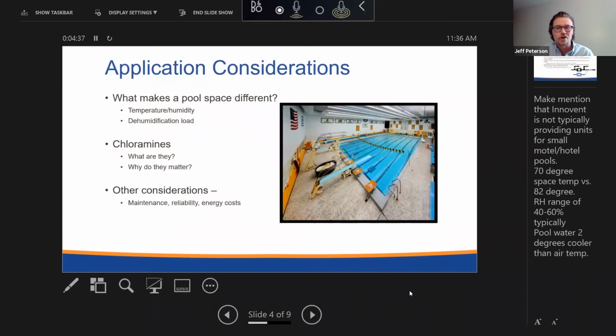So we all know that you don't want a space to get too humid, right? You don't want that humidity level to rise above 60, and the reasons are you don't want mold buildup, mildew, and condensation and things like that. But a lot of people don't realize you also don't want it to get too dry in a space. If your relative humidity gets too low in a pool space, it's going to drive your evaporation rate up, and it can also promote the spread of viruses and things like that. So you want to make sure that you're not over drying those spaces as well.